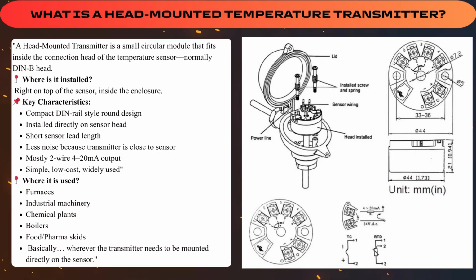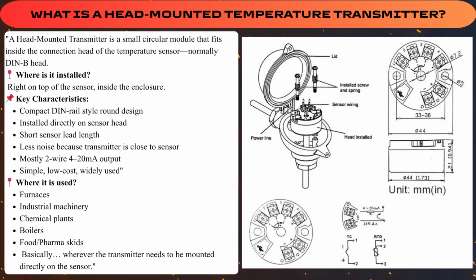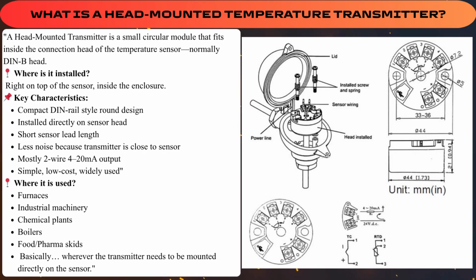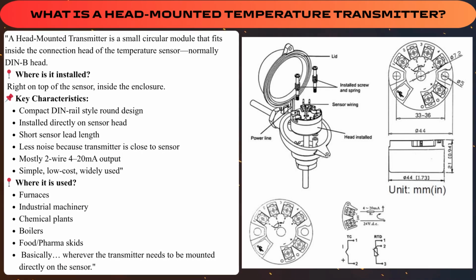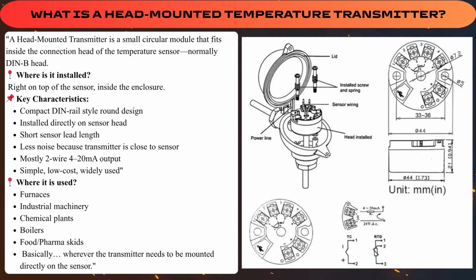What is a head-mounted temperature transmitter? A head-mounted transmitter is a small circular module that fits inside the connection head of the temperature sensor, normally DIN-B head. Where is it installed? Right on top of the sensor, inside the enclosure. Key characteristics: compact DIN-rail style round design. Installed directly on sensor head.